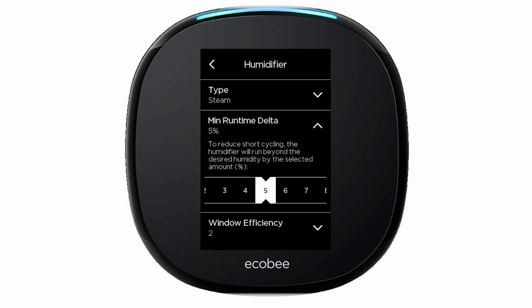You've got your runtime deltas here. So again, going back to talking about equipment and potentially damaging it, this is known as short cycling. So this is where you've got to be careful about short cycling, and you've got to set up those minimum runtime deltas accordingly.